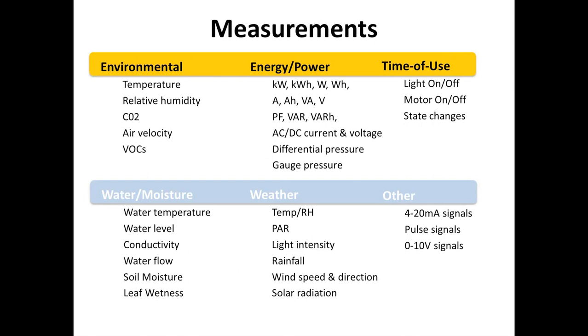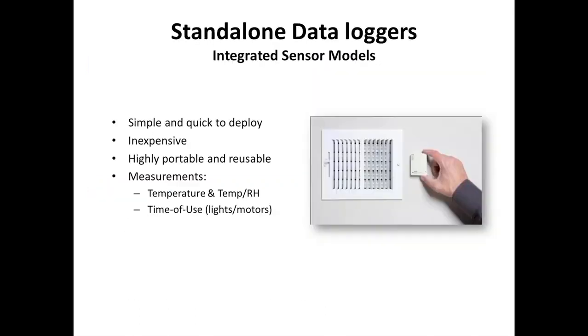Things like weather stations can be set up to look at outside temperature. In buildings, we can look at enthalpy inside the building versus outside the building. We can look at how temperature and humidity outside the building affect the building inside. And we can also hook it up to other equipment that receives different signals and really record an unlimited amount of data.